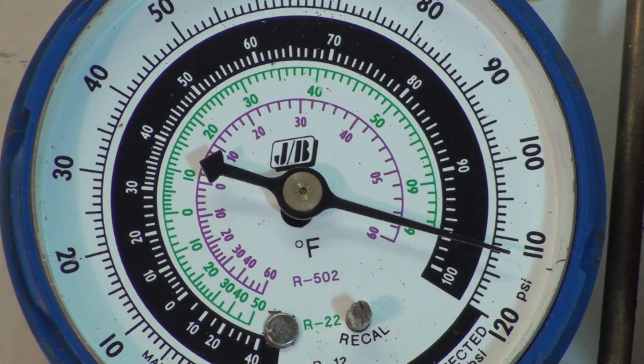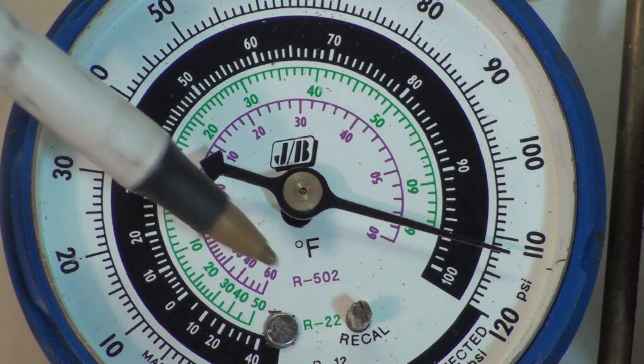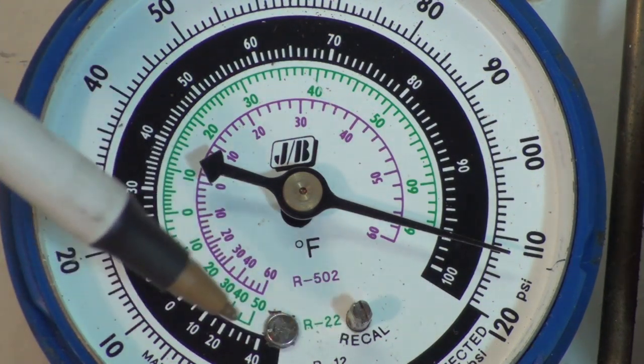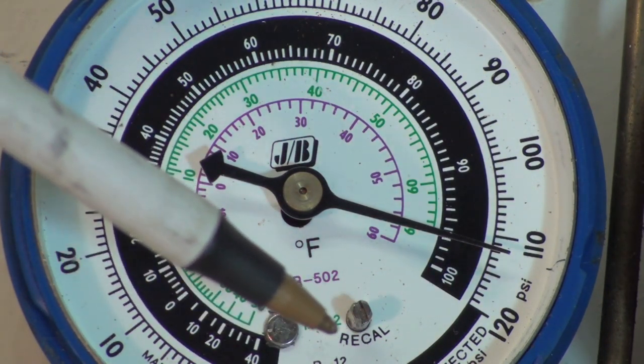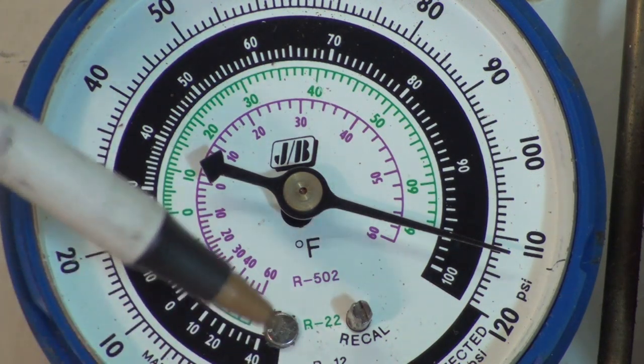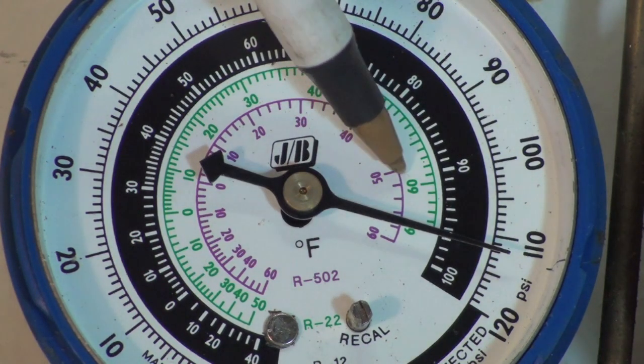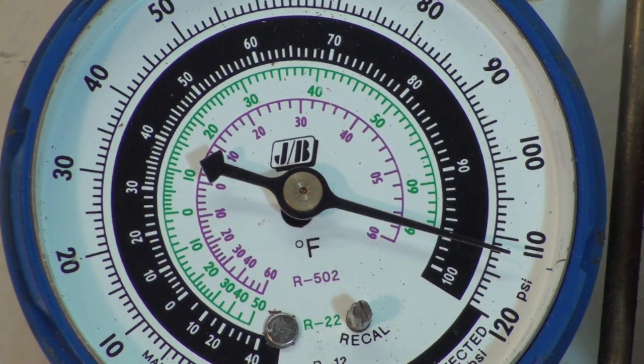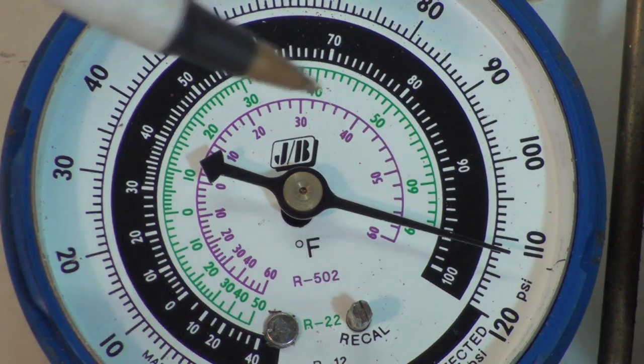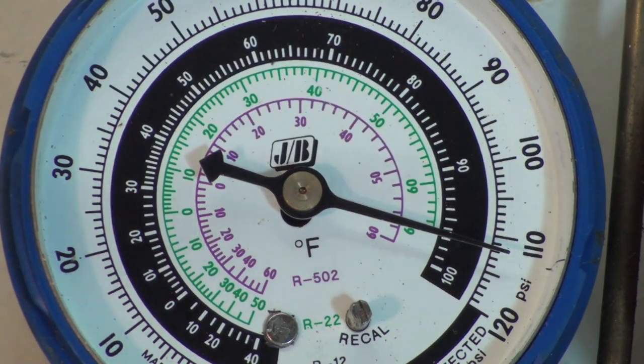Okay, here we've got the compound gauge of the manifold gauge set and we're showing just right at a little under 112 pounds, maybe 111 and a half. If you look on down here you can see it says R12 or R502 and R22. If you follow the green one around, the 22 one which is the second one from the center, you will see that we have 60 here and it goes up to pretty much 65 and we're looking real close to that 65.